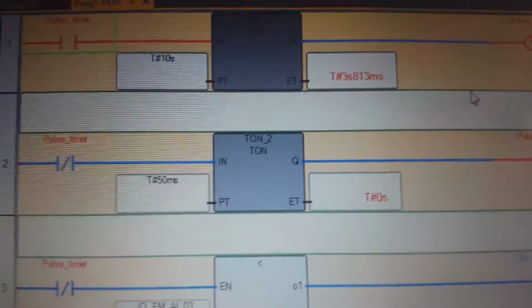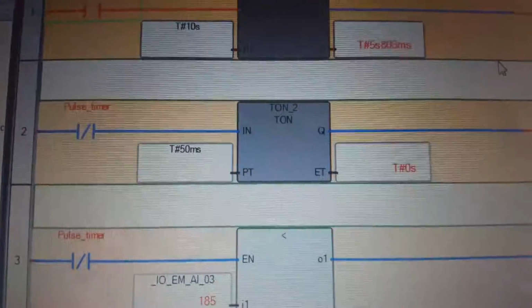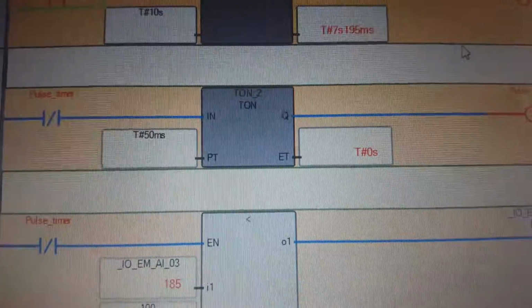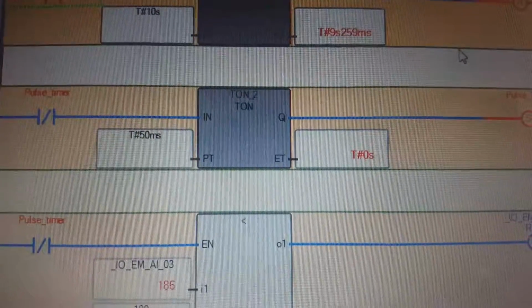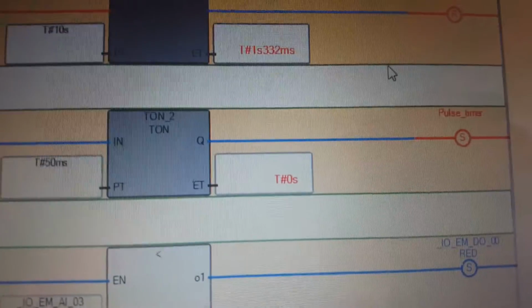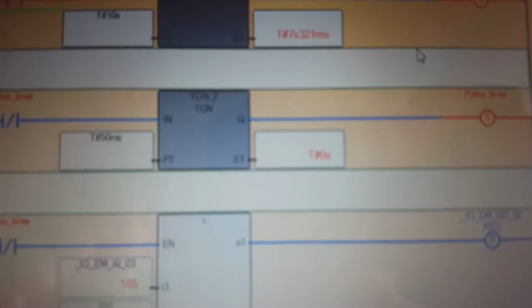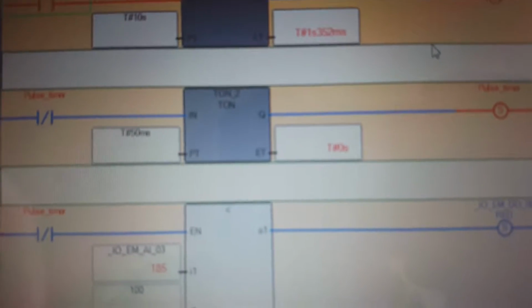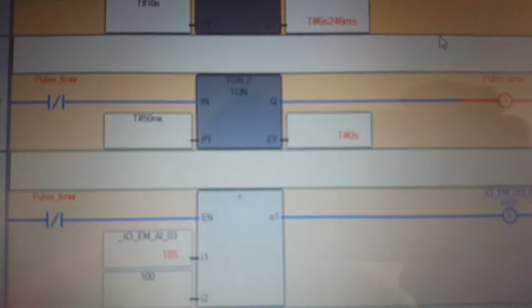This is just so that we're going to get a state for when the 10 seconds the pulse timer will be off, and then for 50 milliseconds the pulse timer will be on, and this is just a way to do PWM off of this variable. So we're getting a really short time that it will be high and a very long 10-second time that it'll be off.